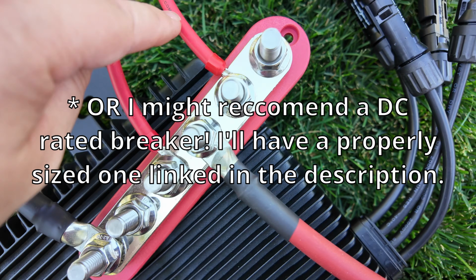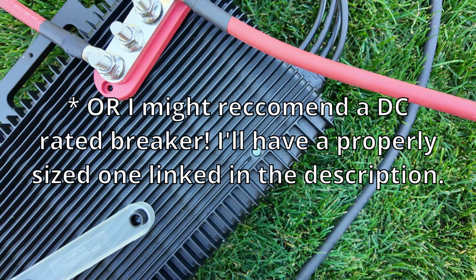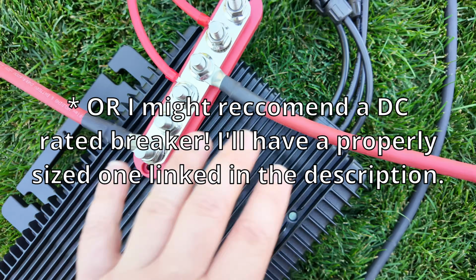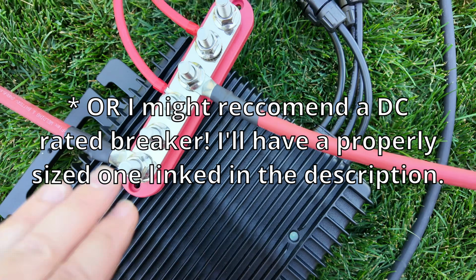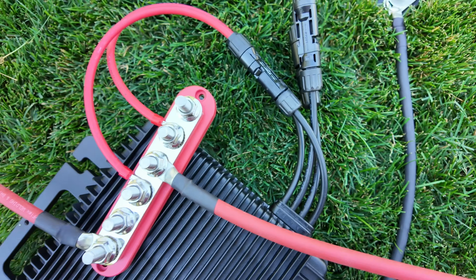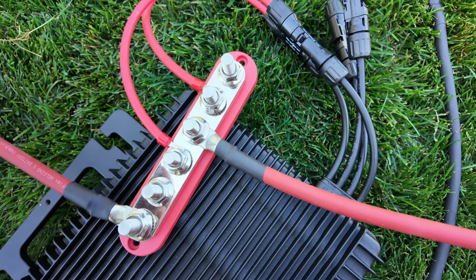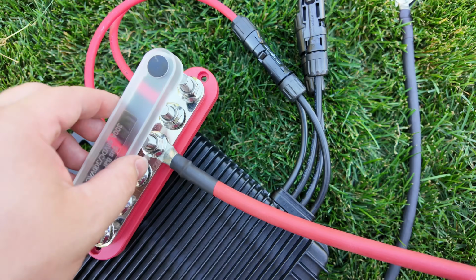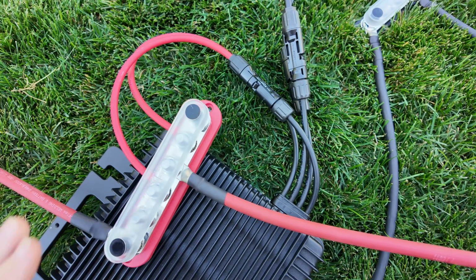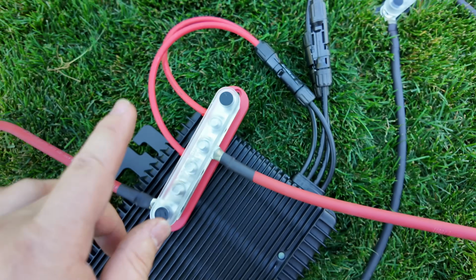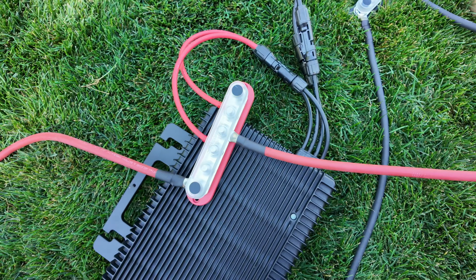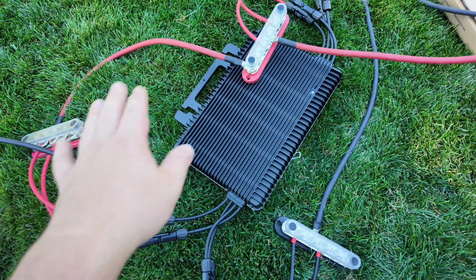On the positive bus bars, one thing I don't have that you should have is a fuse on every cable feeding into the Hoymiles microinverter. That way, if there's any internal short, the fuse will pop and you won't have a fire on your hands. I don't have that right now since I'm just testing this proof of concept, but I'd recommend 20 amp fuses rated above 60 volts. You only need to fuse the positive side.